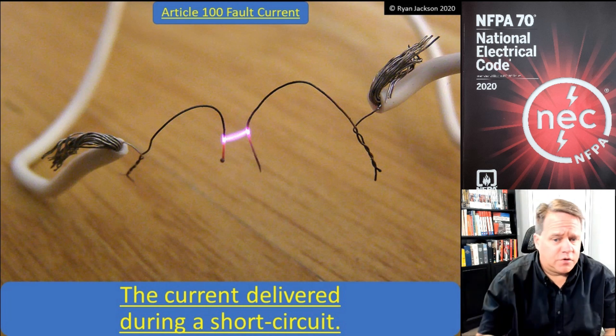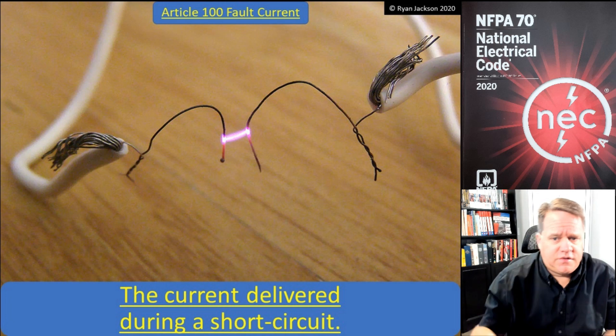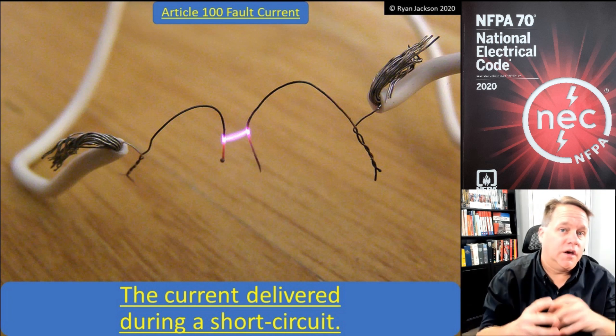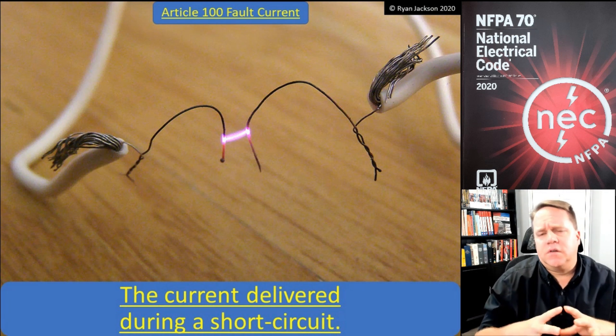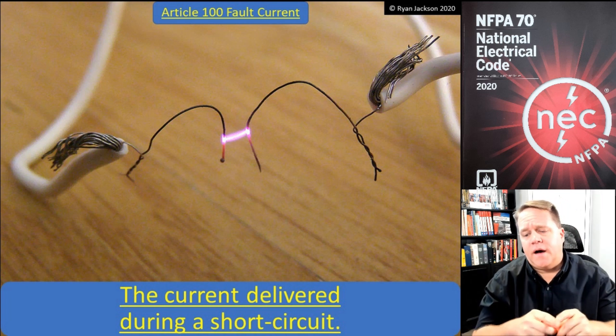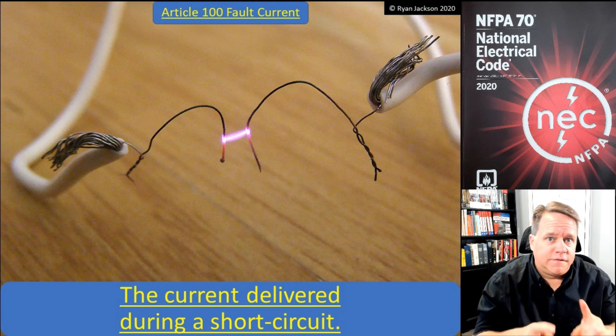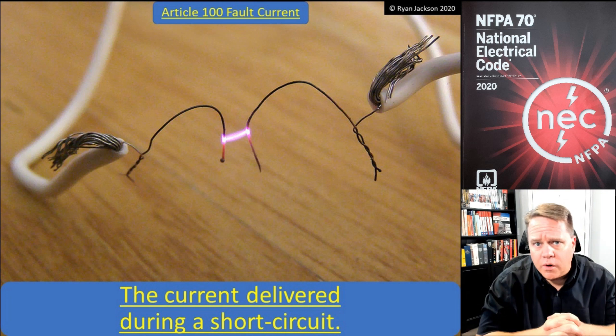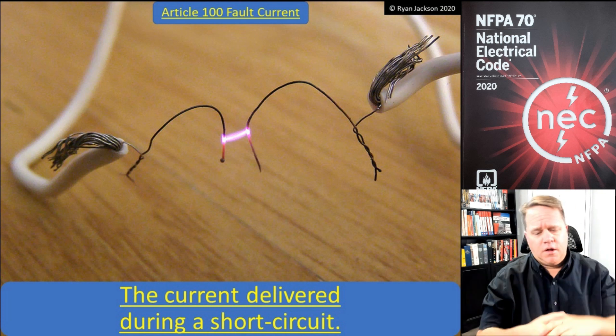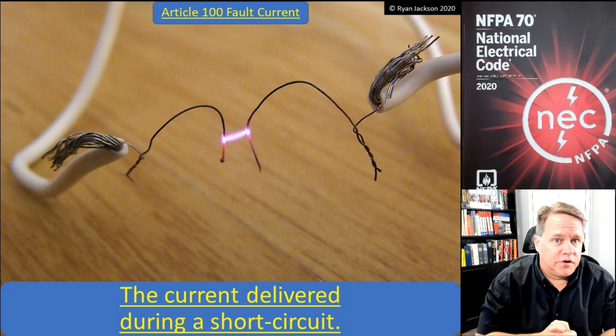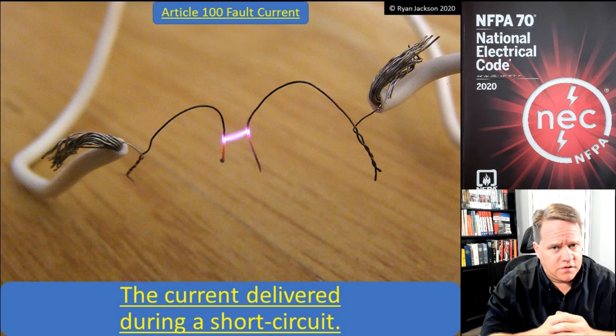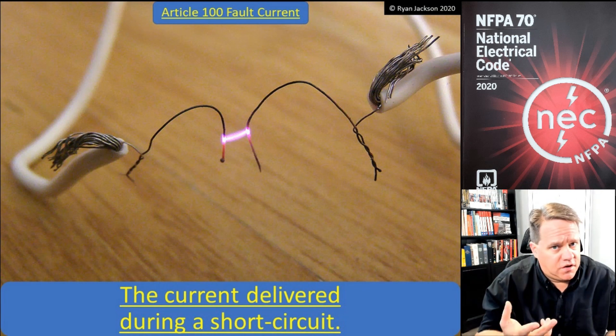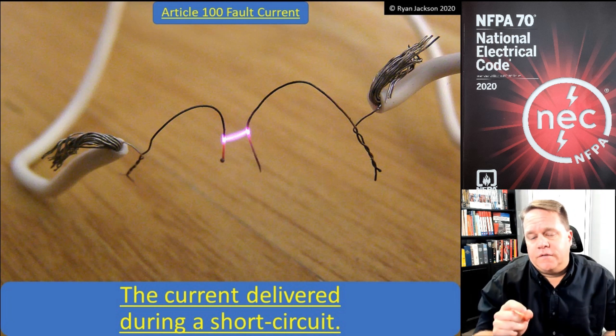Fault current is pretty simple — it's the amount of current that's delivered during a short circuit. The term short circuit is not defined, though it looks like it probably will be in the 2023 code. If I were to define a short circuit, I would include ground faults in my definition. So phase A and phase B smacking into each other, or line one and line two of a single-phase system — the black and red hitting each other — or a line-to-neutral fault like the orange wire hitting the gray wire. I would also consider a ground fault a type of short circuit: an ungrounded energized conductor hitting metal parts connected to an equipment ground. The fault current is the current that's delivered during such an event.